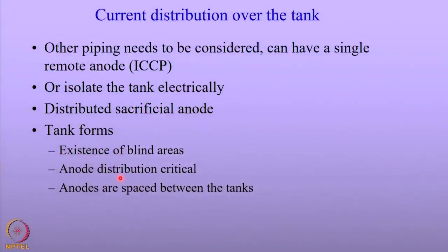In this case, the other pipings need to be considered. You can have a remote anode so that the current distribution becomes easier, or isolate the tank electrically. With a remote anode, you can also account for other pipings connected to the tank.